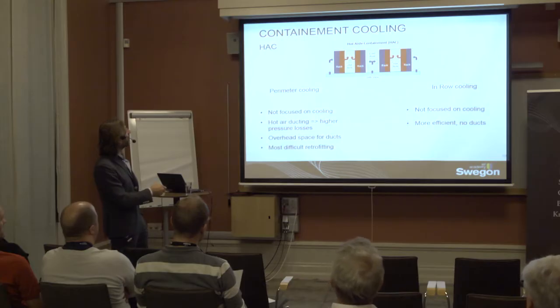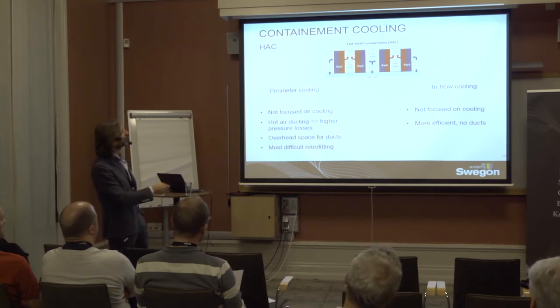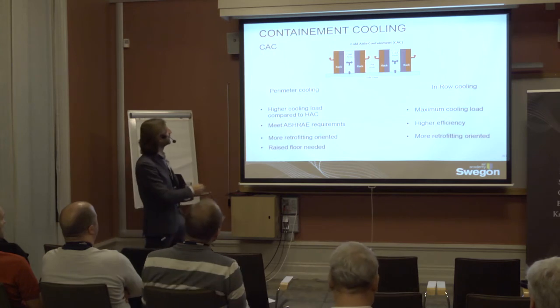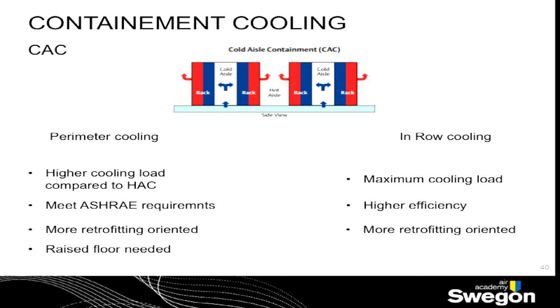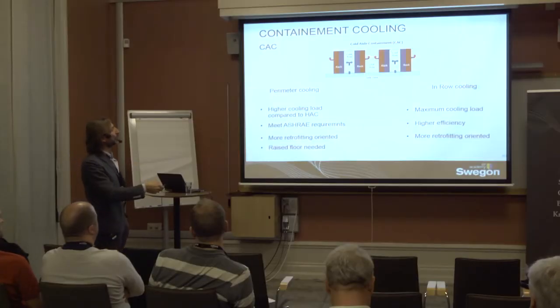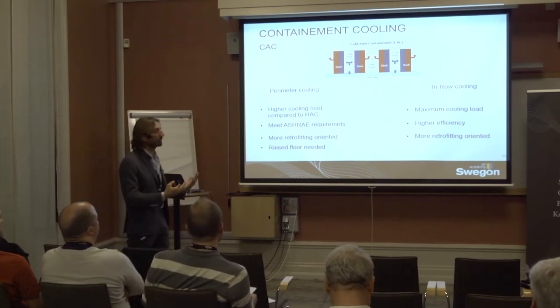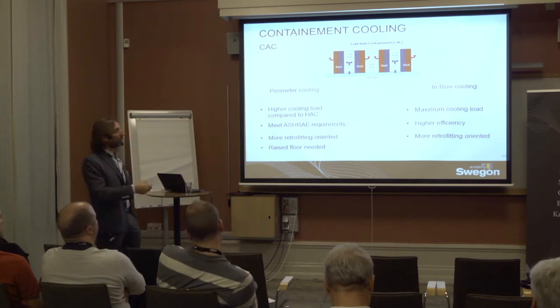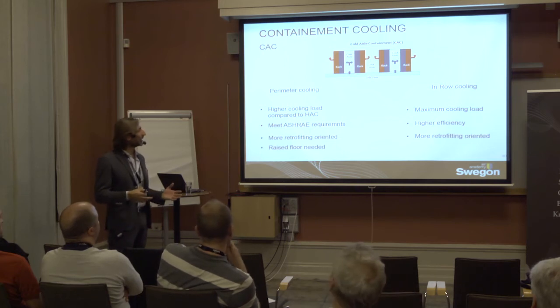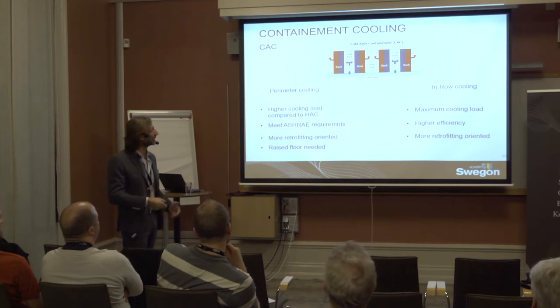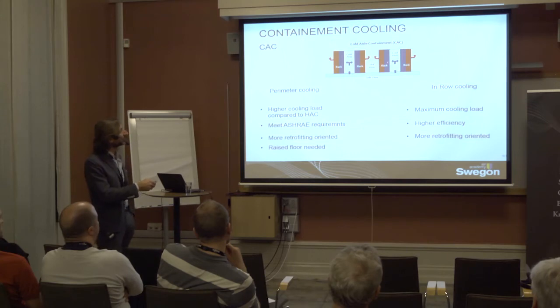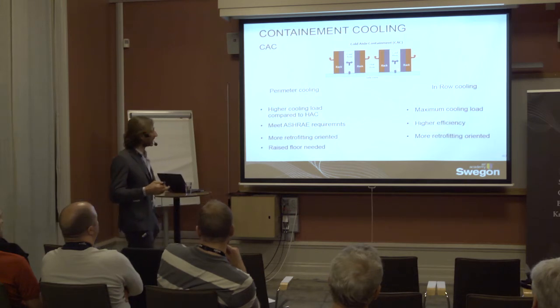So this is combinable with perimeter cooling and with in-row cooling, speaking about the hot air containment. And the same is valid for the cold air containment. Which is the difference? With perimeter cooling, I have to use, let's say, a false floor. So I have the pressure losses connected with the false floor, of course, and with the duct to connect the air from the top of the aisle to the bottom. If I use in-row cooling, of course, I have automatically, let's say, division between hot side and cold side. So only by putting the in-row unit among the servers, I realize automatically the hot and cold air containment. So this is the main difference. And don't forget, this is focused on the temperature on the front of the server, and this is focused on the possibility to increase the efficiency of the cooling system.